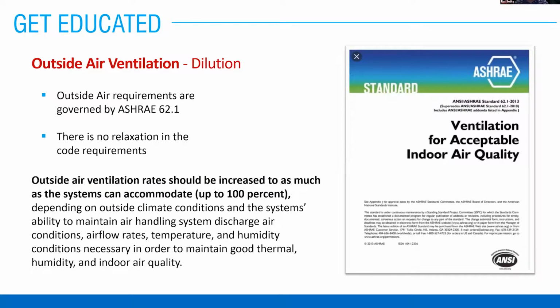Ventilation standards: there is no relaxation in the code requirements as dictated by ASHRAE. What we are looking at is you can increase your ventilation systems up to 100% as long as you do not compromise the thermal comfort and then increase moisture or humidity to the space. So your mandate is always do no harm, but introduce more fresh air.